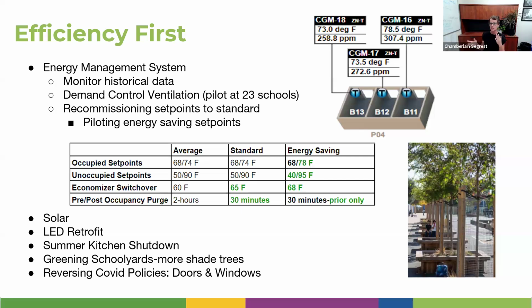We've also added demand control ventilation to 23 schools and are currently reviewing that data for energy trends. The image shows 3 classrooms in this pilot where we can see real-time temperature and CO2 levels. If CO2 reaches a predetermined threshold, the damper opens to pull in fresh air. We're hoping this keeps classrooms feeling less stuffy, so teachers are less inclined to open windows, reducing energy consumption.